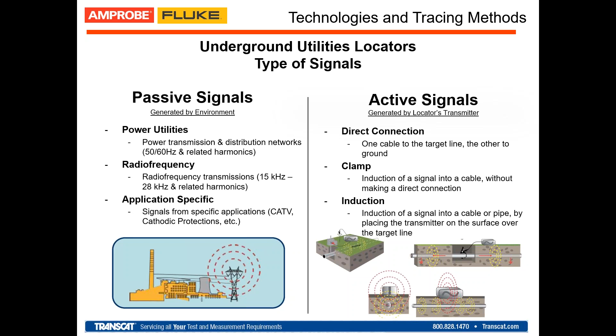And then there are active signals, which is the detection mode used when the transmitter is needed. And when do we need a transmitter? When we don't have any power injected on the circuit, or we have only DC. There are three different ways to use active signals: by direct connection, and I'll explain that later, by clamp, and by induction. So three ways to inject a signal with an underground locator into an electric circuit.